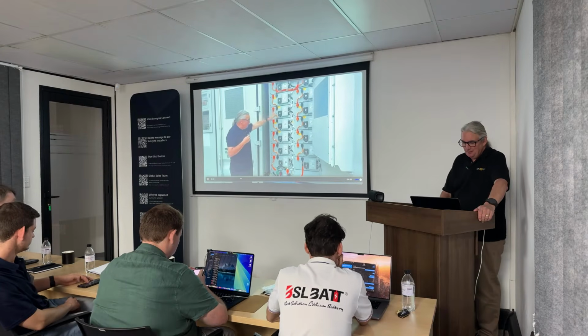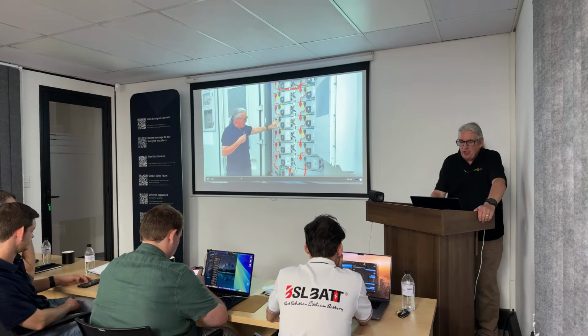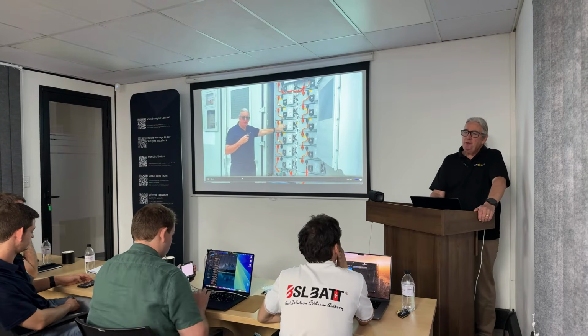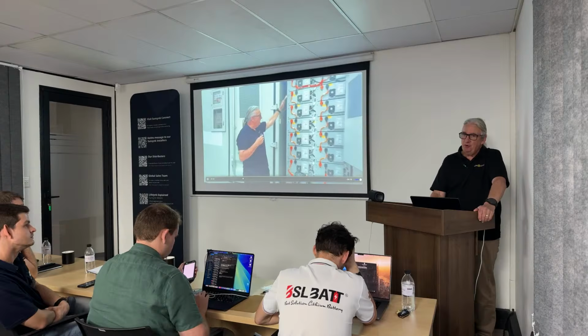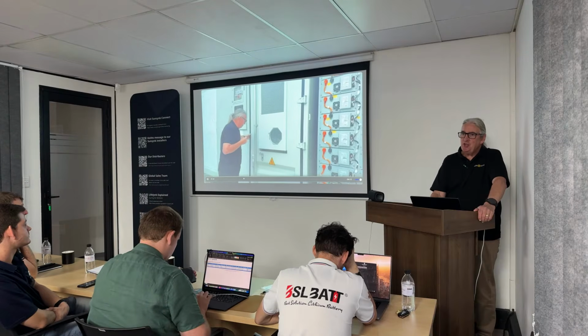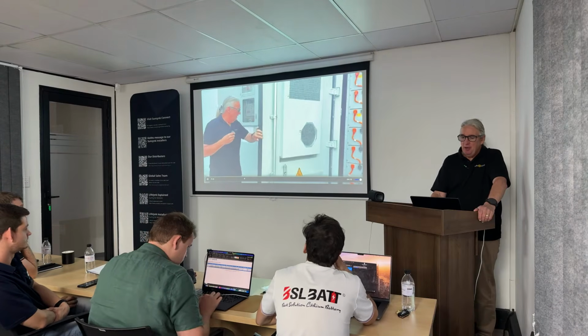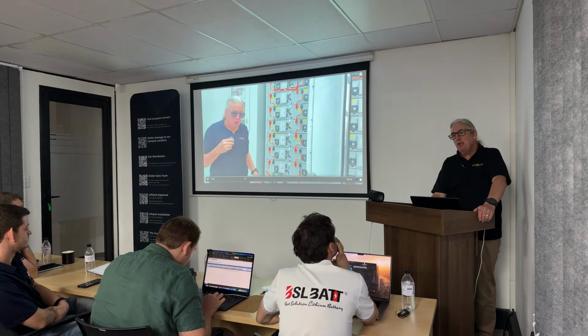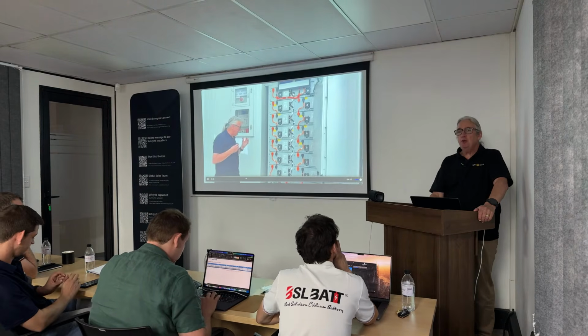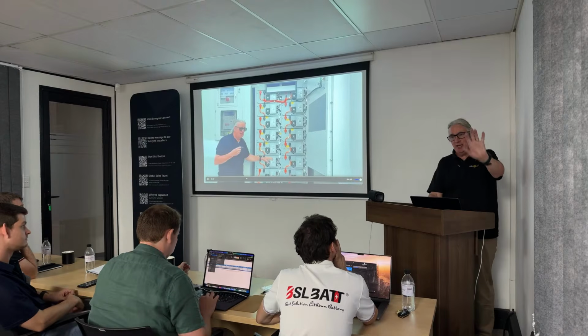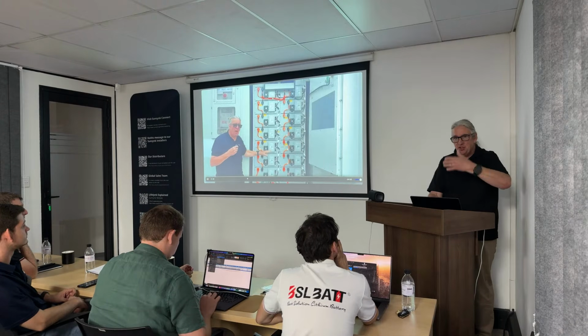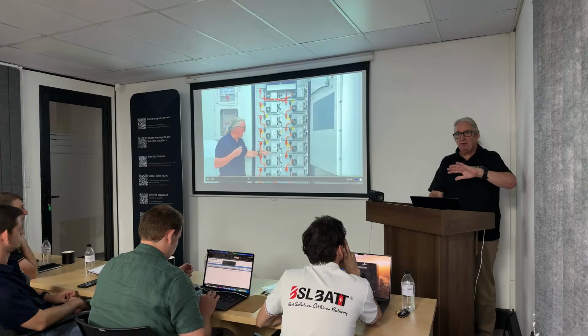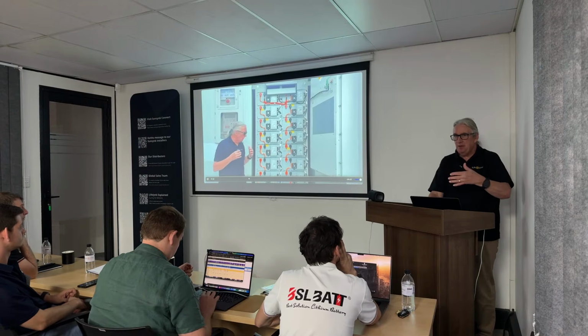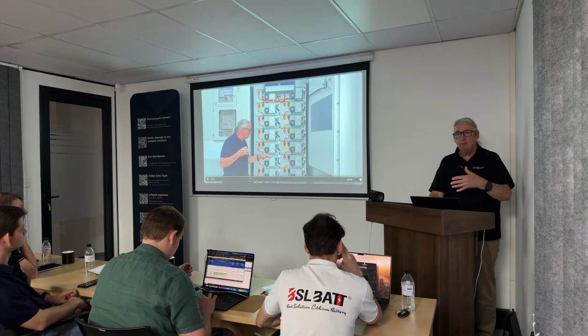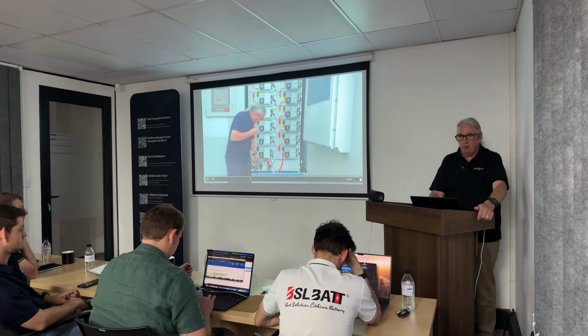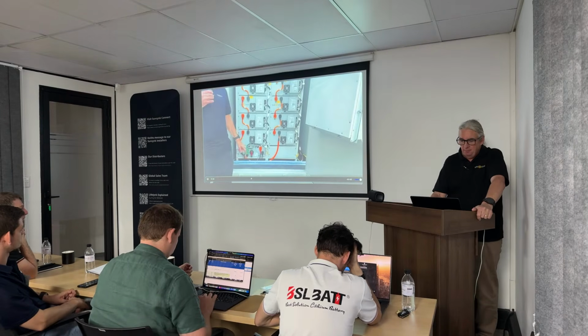Each one of these packs of batteries - I'm talking about parasitic losses, where if you're running a cooling system 24/7, the amount of energy you'd be drawing and using is significant. These systems use a liquid coolant, so they don't take air from the outside in - it's circulated internally, so it doesn't pull air through. It's a sealed system, coupled by a coolant, but we don't use water flowing through all of the electronics - the battery management unit.